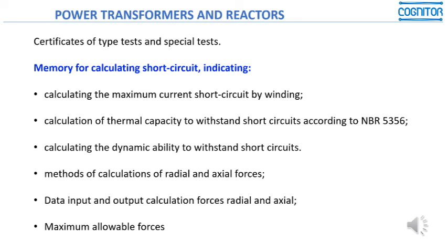In these calculations, usually you do a calculation of electrodynamic stresses in the transformer and a calculation of the thermal capacity to withstand short circuits in the windings. This is usually done when it's not possible to carry the transformer to a testing lab, or if the transformer is too big to be tested in a certain laboratory.